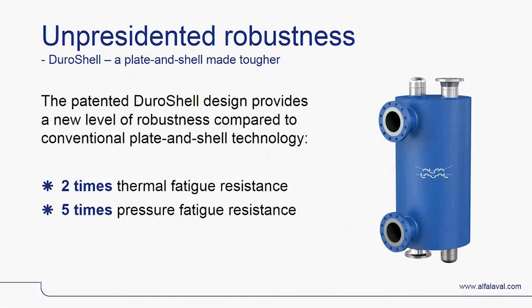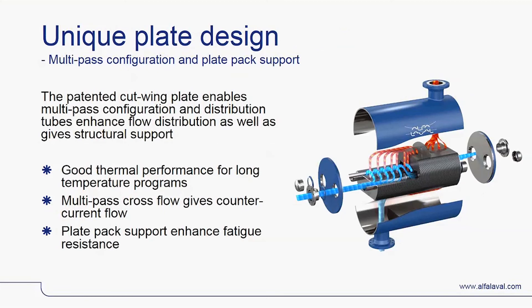For the second offering to the offshore gas industry, we have DuroShell, which will also address the space and weight limitations and the need for maximum uptime. The patented Alfa Laval DuroShell heat exchanger provides a new level of robustness compared to conventional plate and shell technology, delivering a two times improvement on thermal fatigue resistance and a five times improvement on pressure fatigue resistance. The robustness and superior thermal performance comes from the core of the heat exchanger: the unique cut wing plate with our patented roller coaster pattern, together with distribution tubes going through the whole heat exchanger.